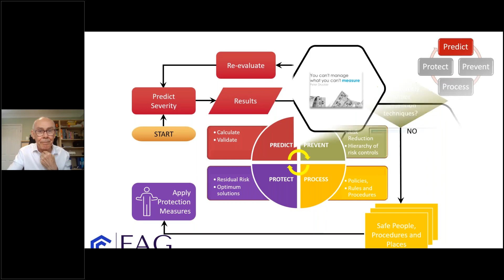So if you have a look in the top right, there is a little wheel showing where we are: predict, prevent, process, and protect. We're actually in the predict section here, and what I'm going to highlight is arc flash calculations, which is what we use for predicting the level of the hazard. In this particular case, we're going to look at IEEE 1584, the guide for performing arc flash calculations. There are other predictive techniques, but this creates an incident energy level, which would be at the worker themselves. But I do discuss much more than this within the book itself.